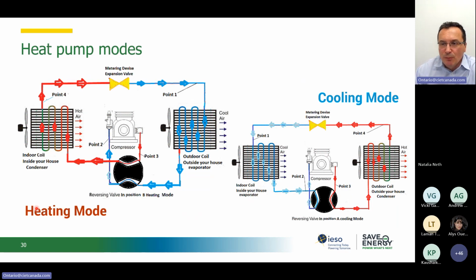So just to show how the two modes operate, this diagram here shows the reversion that happens in the flow. They are basically valves that automatically switch the direction of the refrigerant flow, and the two heat exchangers exchange roles. So in heating mode, we have the condenser inside. That's where we dump the heat. So this is our sink, and then outdoor would be our source. So this is the evaporator outside. And then the two reverse roles in cooling mode.